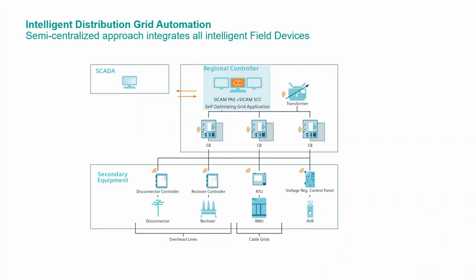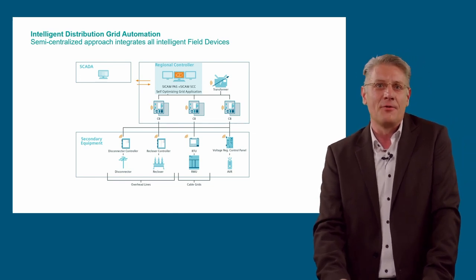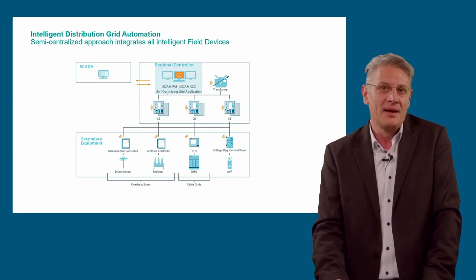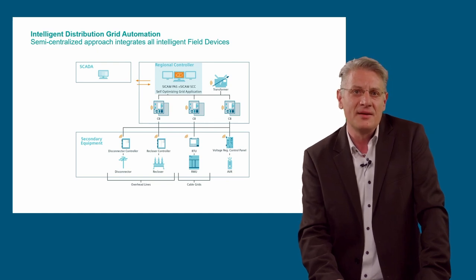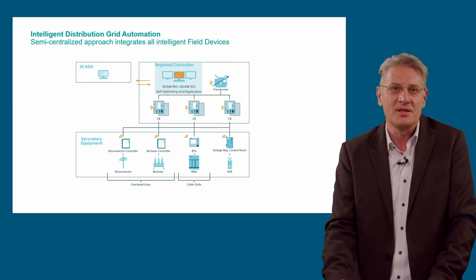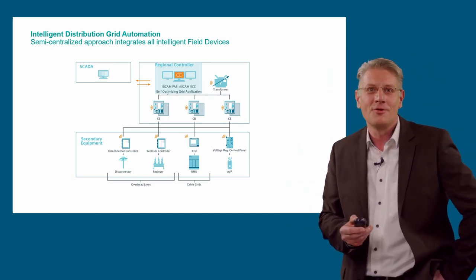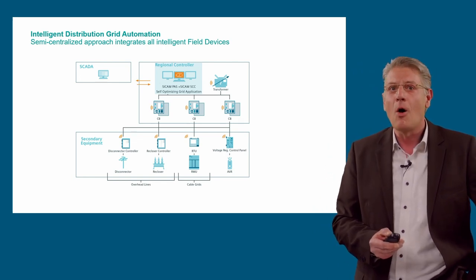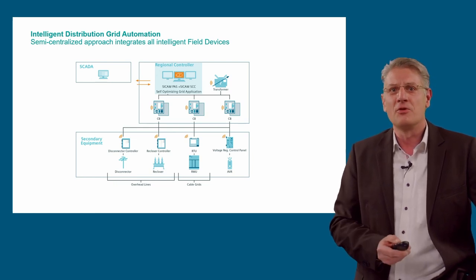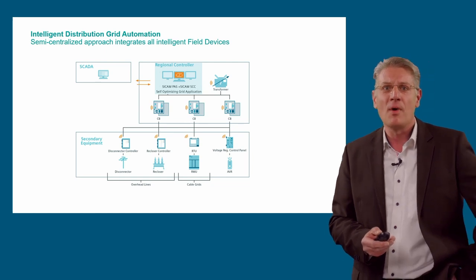The semi-centralized approach integrates all field-level devices. Let's have a closer look at the system architecture of our self-optimizing grid and how the application is integrated in our secondary systems. Our application is based on standard substation automation products. The regional controller of the self-optimizing grid is hosted in the automation system SICAM PAS, and the human-machine interface is located at SICAM SCC — the blue rectangular in the middle. The regional controller can be placed directly in the primary substation or can supervise multiple primary substations. Directly connected to it are intelligent field devices and such as protection relays and transformer controllers. In the secondary equipment section, you find equipment for handling overhead lines, reclosers with recloser controllers, cable grids with ring main units and remote terminal units, and voltage regulators like RONs or pole-mounted AVRs.